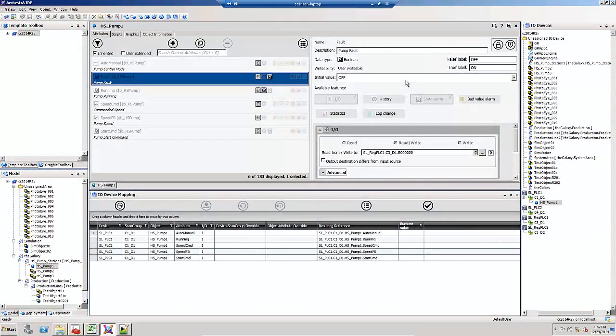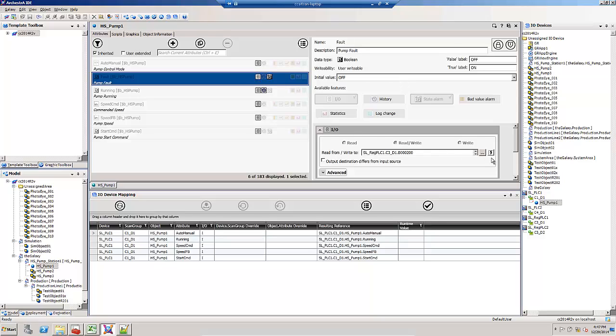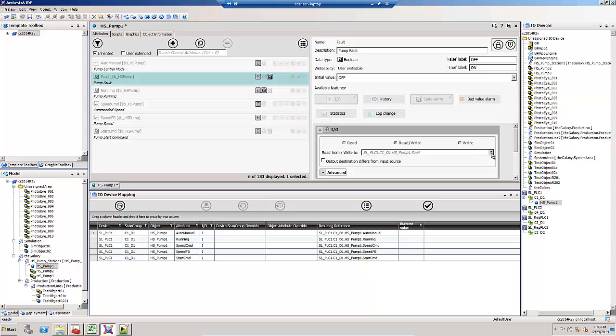If I wanted to return this hard coded reference back to being mapped automatically, I could open it up for editing. There's this lightning bolt button on the I.O. reference. I've got the fault attribute highlighted. I've got my I.O. extension shown with the I.O. reference. If I hit the lightning bolt, notice how the font changes. It changes it back to being auto mapped.